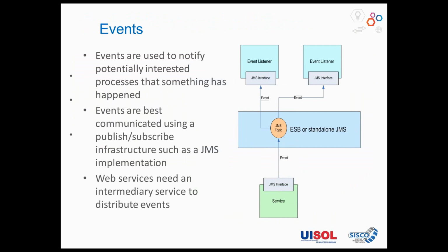Then you have events. So an event might be something, for example, a meter may send out an event such as a last gasp message, and that's going to go out to the AMI system, the automatic meter infrastructure system, but then it's going to go through an ESB, and you may have different event listeners. So you may have an outage management system sitting out here listening. You can have a historian sitting out here listening that's going to track that stuff and store it.